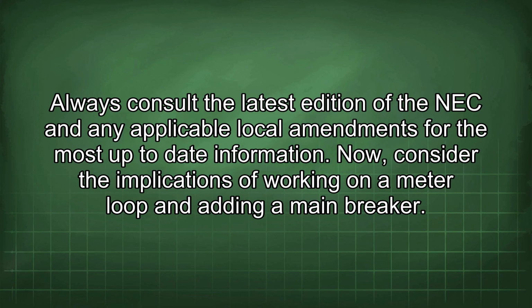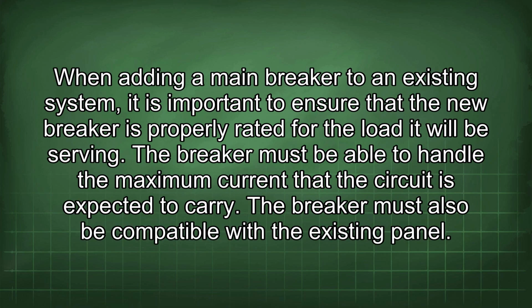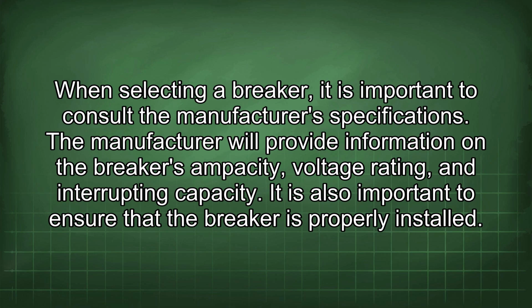Now, consider the implications of working on a meter loop and adding a main breaker. When adding a main breaker to an existing system, it is important to ensure that the new breaker is properly rated for the load it will be serving. The breaker must be able to handle the maximum current that the circuit is expected to carry. The breaker must also be compatible with the existing panel. When selecting a breaker, it is important to consult the manufacturer specifications. The manufacturer will provide information on the breaker's ampacity, voltage rating, and interrupting capacity.